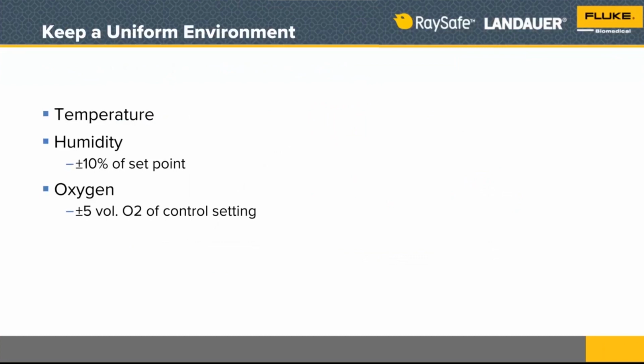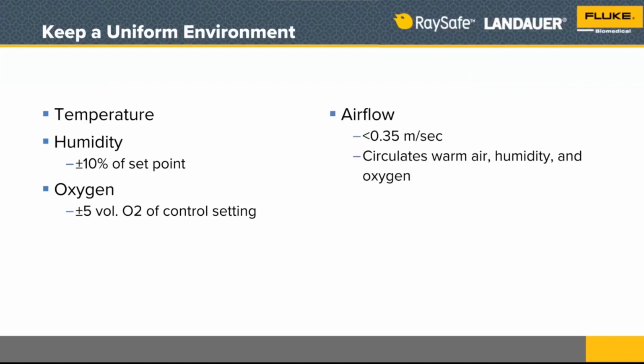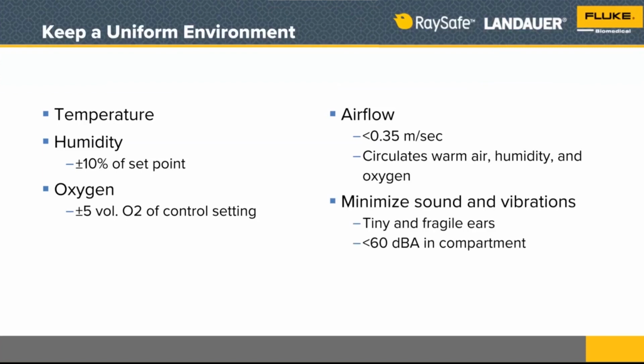So what we want is to keep it in the uniform temperature, humidity, and the humidity should stay plus or minus 10% of the set point. Please mute yourself if you come unmuted. Oxygen needs to be plus or minus 5% of whatever our control setting is. And we'll get to why those are important. Airflow should be less than 0.35 meters per second. Circulates the warm air and humidity and the oxygen in the chamber.